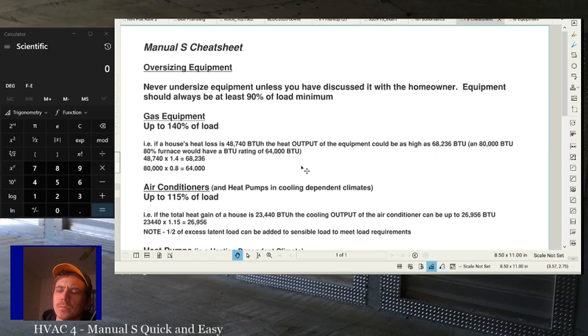All right, so the most important thing is how much you can oversize equipment, right? Because you should never undersize equipment unless you discussed it with the homeowner and they understand that the cooling performance and the heating performance may not quite get to the design temperatures on load days, right? So, for our area, for Fairfax, Virginia, your design days are 95 degrees outside. You should be able to maintain at least 75 degrees inside. At 17 degrees outside in heating, you should be able to maintain at least 70 degrees inside, right? And cooling, we were trying to maintain 50% humidity generally, right?